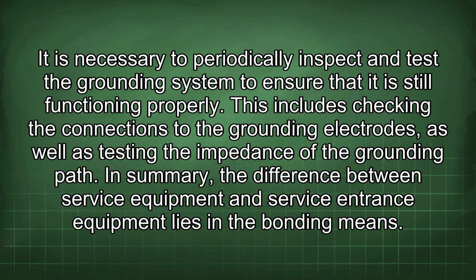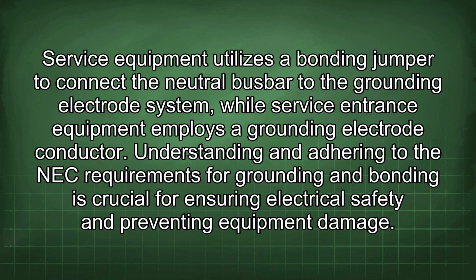In summary, the difference between service equipment and service entrance equipment lies in the bonding means. Service equipment utilizes a bonding jumper to connect the neutral busbar to the grounding electrode system, while service entrance equipment employs a grounding electrode conductor. Understanding and adhering to the NEC requirements for grounding and bonding is crucial for ensuring electrical safety and preventing equipment damage.